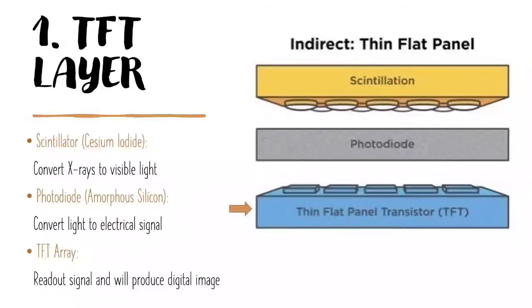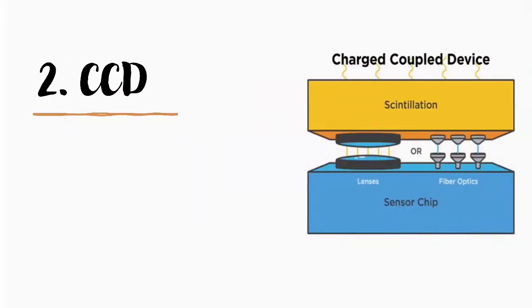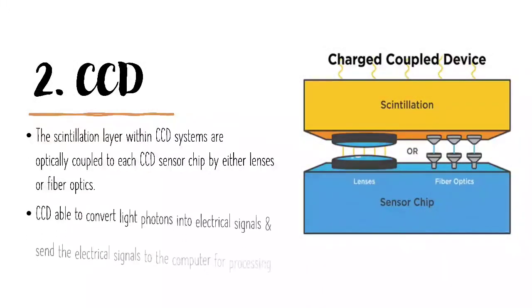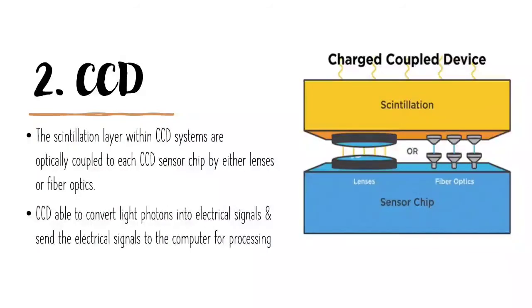Moving on to the next one is CCD. The scintillation layer within the CCD system is optically coupled to each CCD sensor chip by either lenses or fiber optics. CCDs are able to convert light photons into electrical signals and send the electrical signals to the computer for processing.